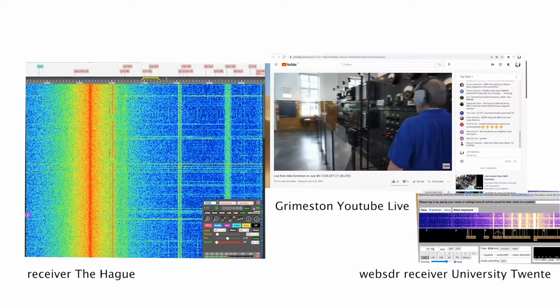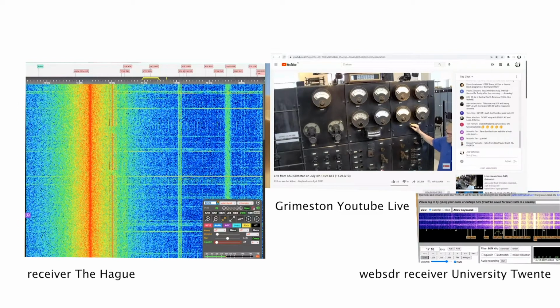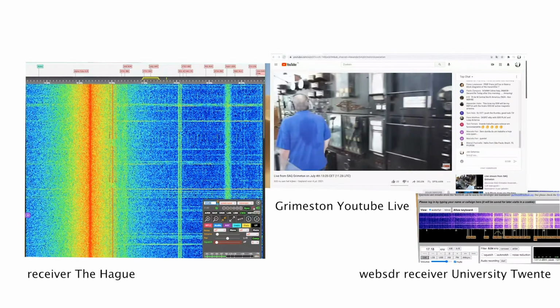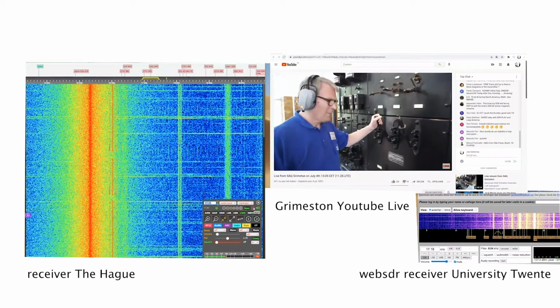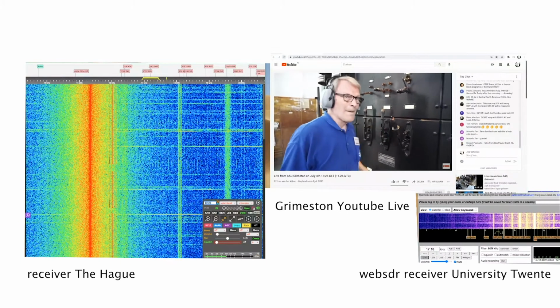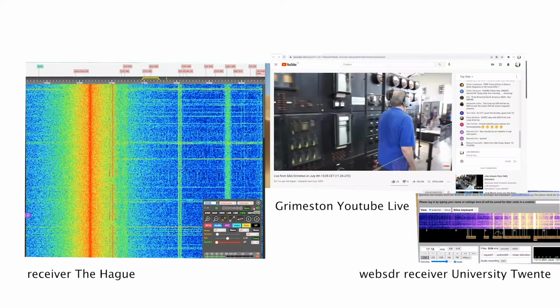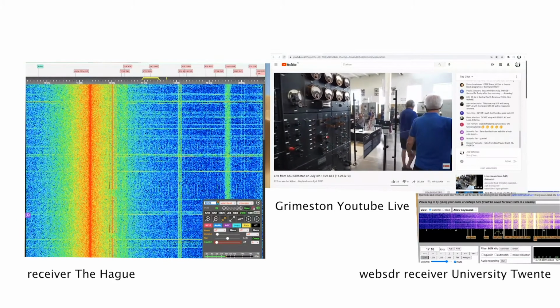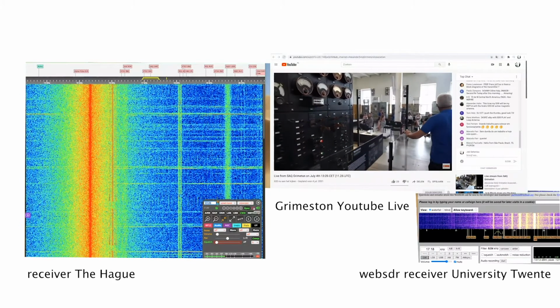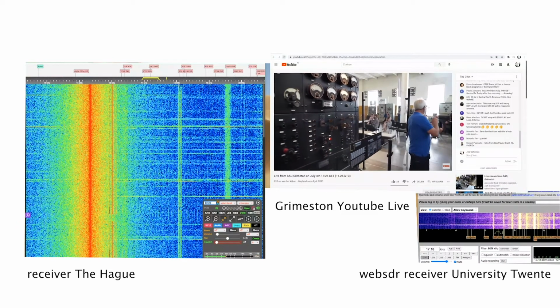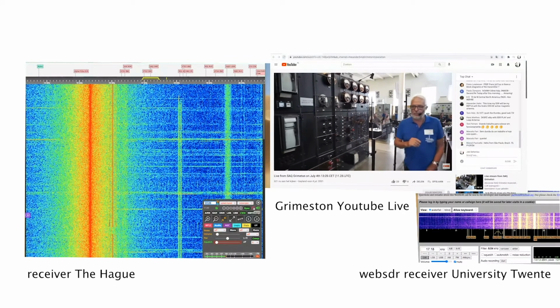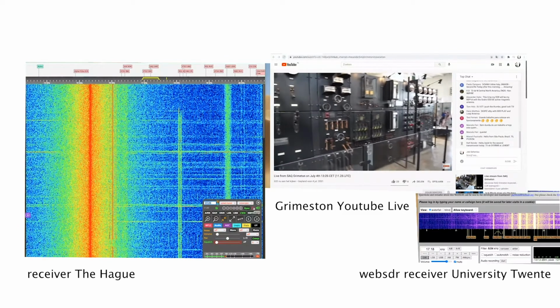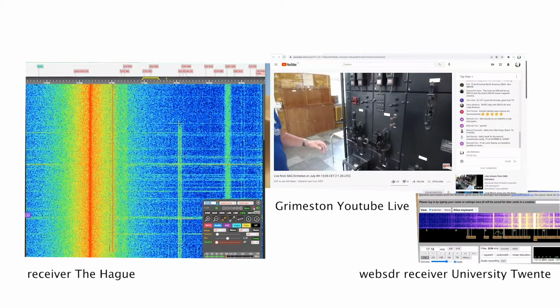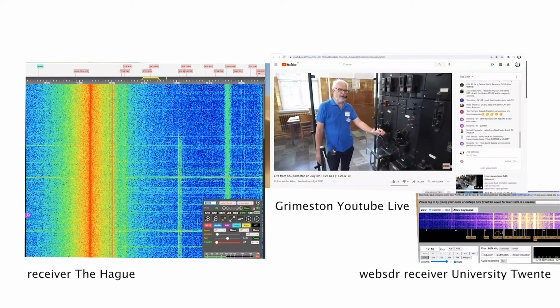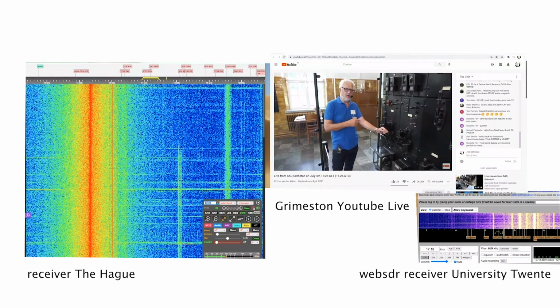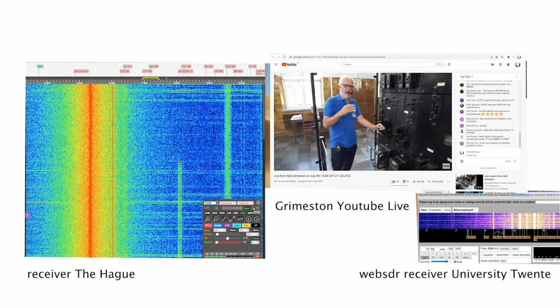Now we are back at the control panel, and we add the alarm bell again. We have an alarm because we have no oil pressure in the system, and to solve that we start an auxiliary oil pump. Now that provides oil pressure to the alternator bearings and to the gearbox. Now we are prepared to start the transmission unit, and Jan-Åke is back on the emergency stop. To protect the main motor, the initial current is limited by transductors on line with the power supply, and we also have high resistance on the rotor.